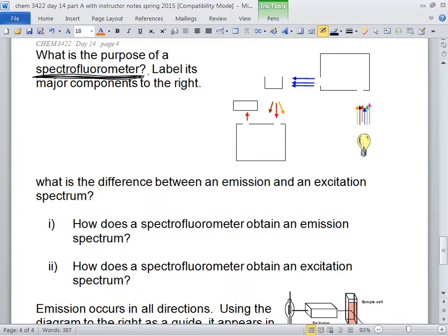We wanted to isolate the compound, and we did. It worked really, really well. So why isn't it hooked up? It's not hooked up because it's very user unfriendly, and the consequences of not following the instructions to turn it on are huge. You have to push one button and then you push the other button. If you don't do it in the right order, you see a little puff of smoke in the back, and this about $1,000 lamp completely gets burned out.